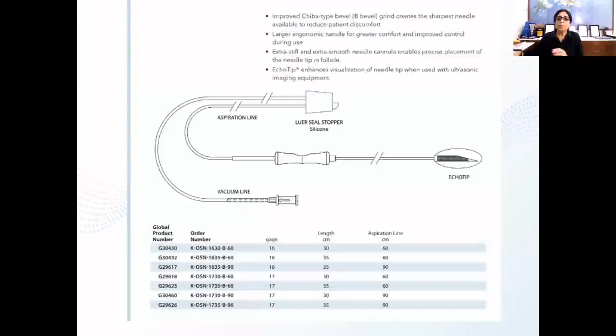So now over here, there are 2 options. As you can see, this can be 60 centimeter or 90 centimeter. If it's 90 centimeter, the whole system can go a little farther away. Suppose you do not have a single test tube holder and you want to keep these round bottom test tubes on a table where the test tube warmer is kept. That is the whole heating block which needs to be kept on a table. Then you may need a longer length of the aspiration line. But if you have those single test tube holders, then 60 centimeters is good enough.